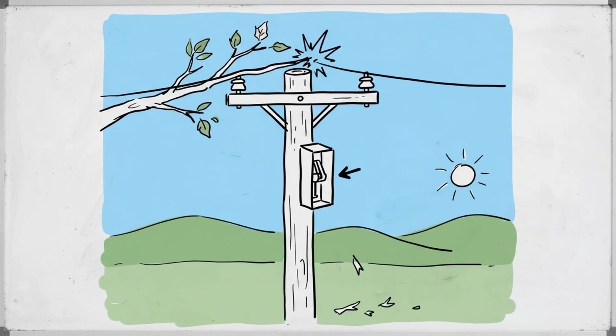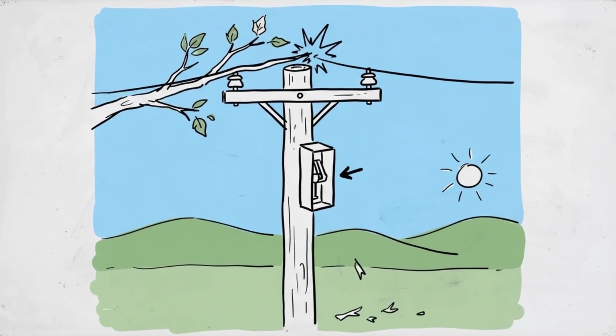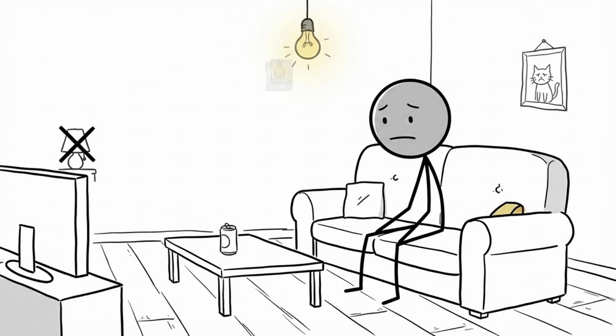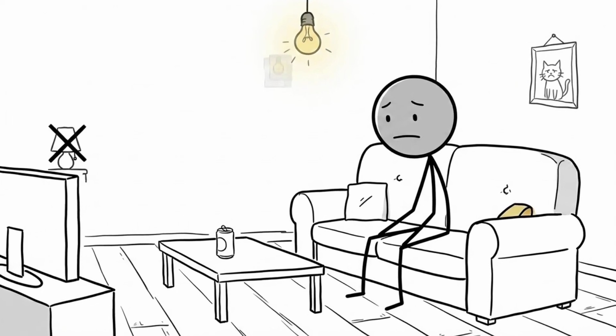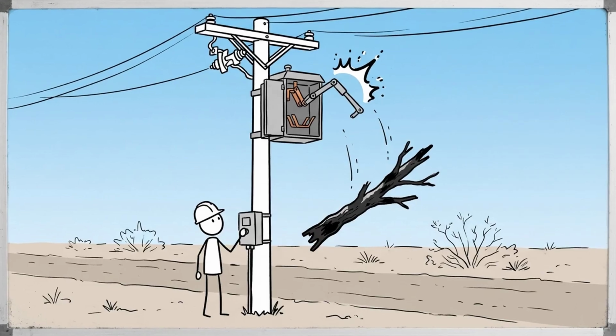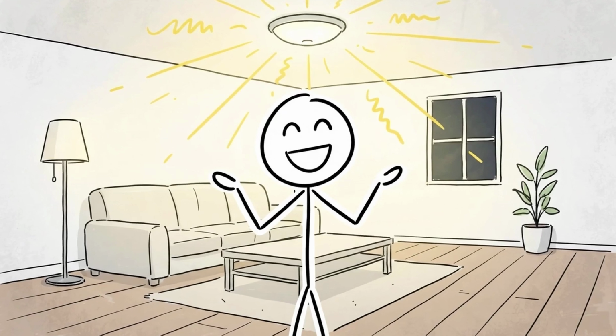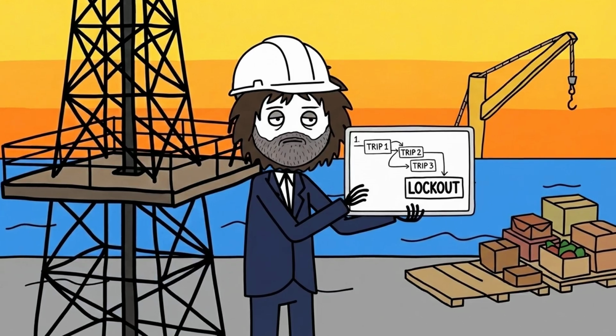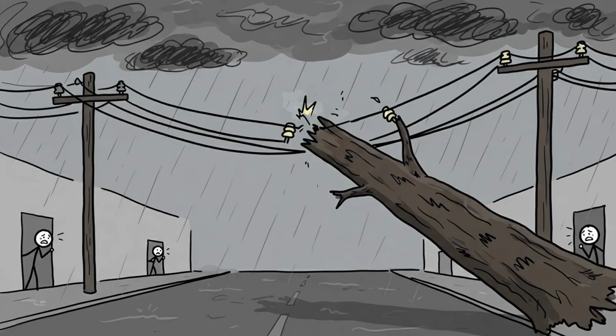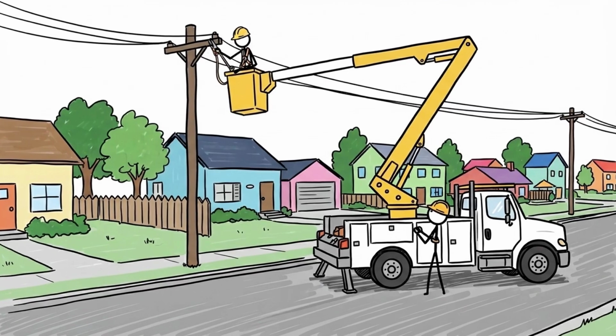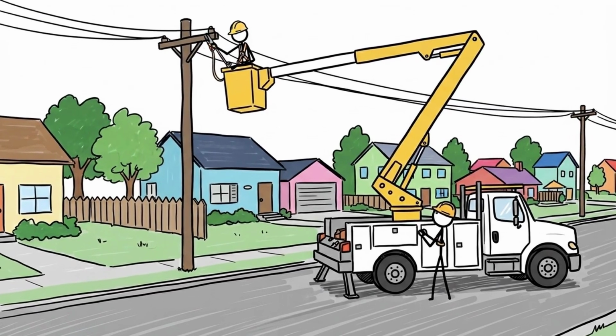You will also find automated switches called reclosers mounted at the substation exit. When a tree branch momentarily brushes against a power line in a windstorm, the recloser quickly trips open and then automatically closes back up 3 times to clear the temporary fault, which is why your lights often blink several times before either staying on or going out completely during a severe storm.